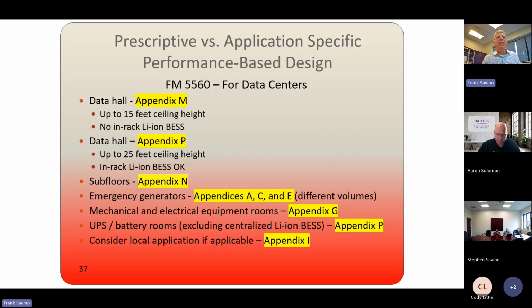Just to review, for data halls, it's Appendix M. That's for ceiling heights up to 15 feet. Data hall, Appendix P, ceiling height up to 25 feet. And you can include under Appendix P, a lot of these in-racks have built-in lithium-ion batteries. You can use water mist for that application.